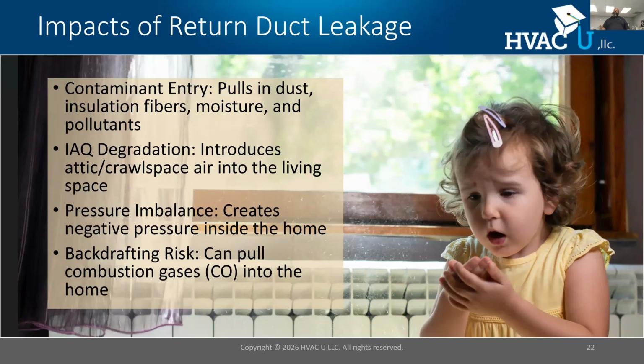It's going to bring in that unconditioned air into the duct system. It's going to increase our load and it's going to decrease our capacity. However, air from an attic or crawl space often isn't the best place to get air from. Well, why is that? What's in the air inside an attic or crawl space? We have rodent activity, possibly, maybe mold spores or fiberglass fibers, any host of indoor air quality issues that can cause some type of respiratory ailment.